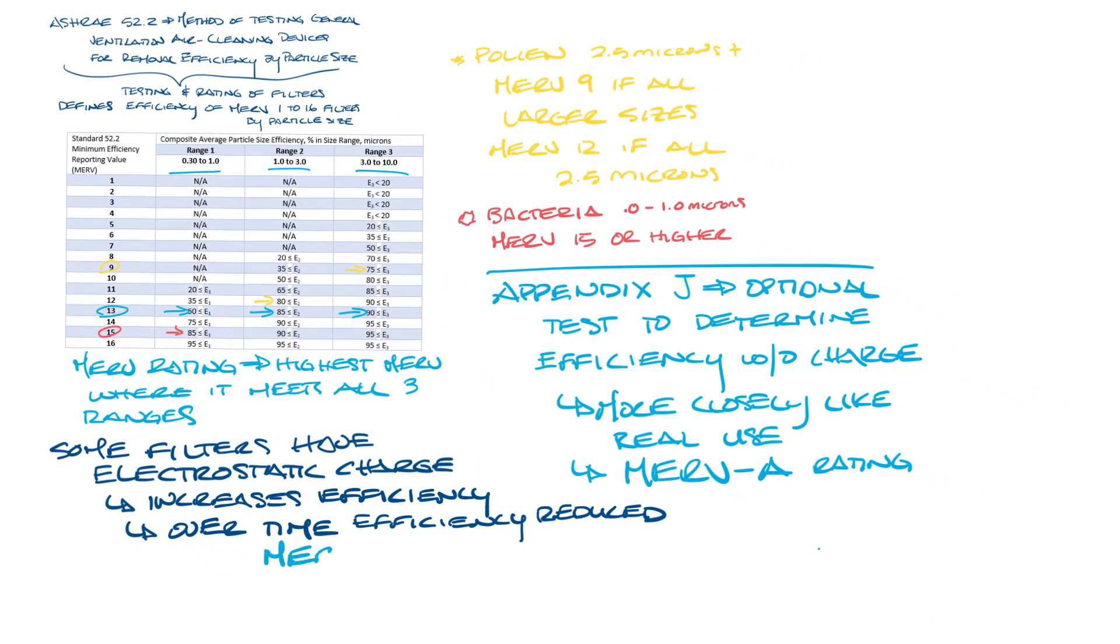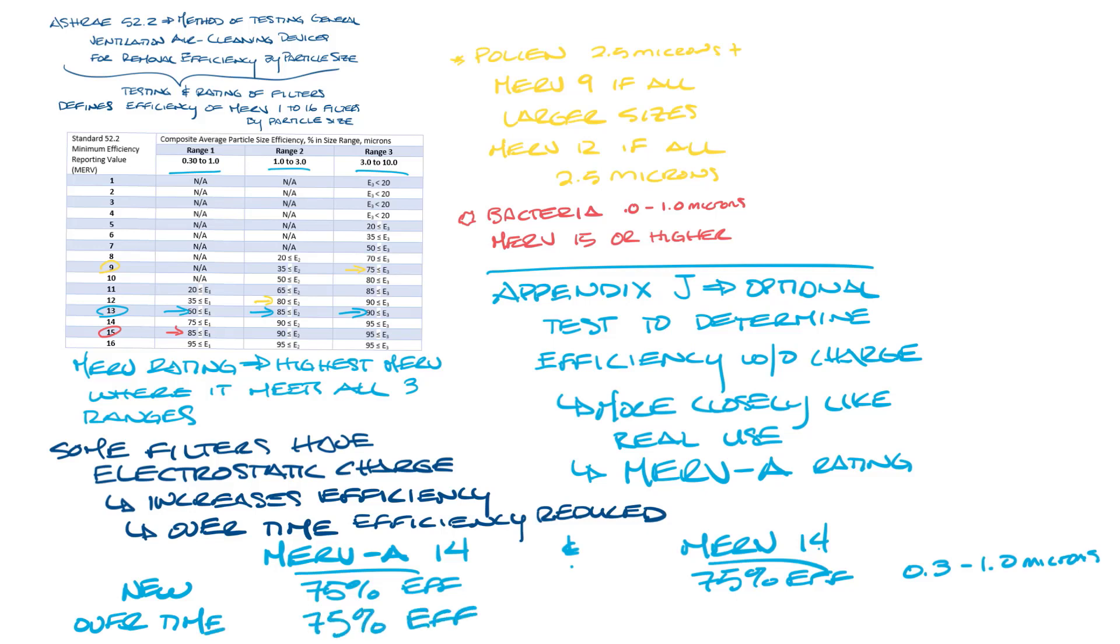For instance, a MERV-A 14 rated filter and a MERV 14 rated filter that has an electrostatic charge may perform the same when new, capturing 75% of the 0.3 to 1 micron particles. But after some use, while the MERV-A 14 filter will still have 75% efficiency, the MERV 14 could drop to effectively a MERV 12, which only captures 35% of those same particles. And that's a pretty big drop in performance.